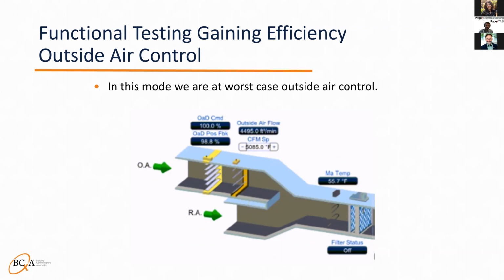Now, obviously, if you have a dedicated outside air unit that delivers outside air to the AHU, you will not need a return air damper, but it's still a good time to make sure that the DOAS has enough power to deliver the outside air without much help from the AHU.